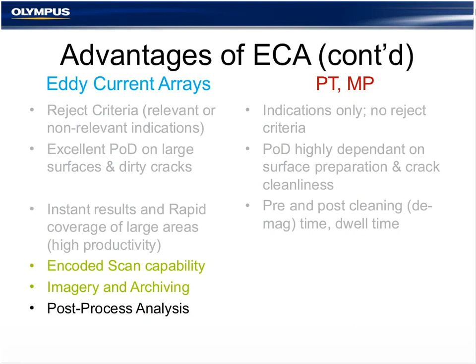The equipment used now in that solution is the OmniScan MX flaw detector, plus the pipe kit that we call the SCC probe, which gets you a flex array, a set of wedges, an encoder, a standard calibration standard, and a standard practice. Olympus already has some recommended instructions on how to set up, plus not an ECA inspector, but a certified eddy current testing inspector. So the same person that operates that Nortec for any duties can be using the OmniScan eddy current array flaw detector without being too much lost.